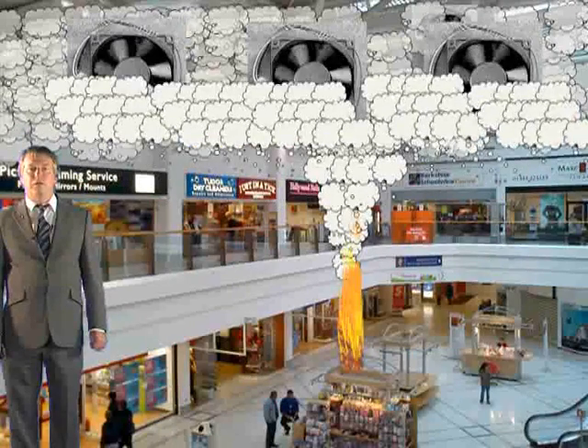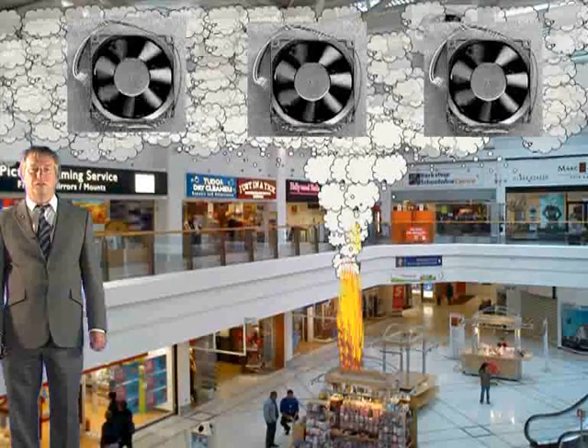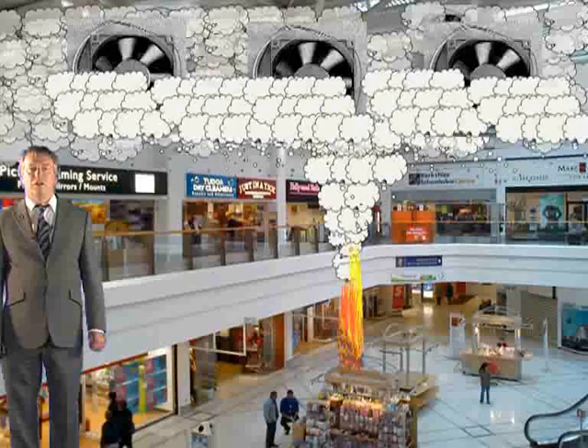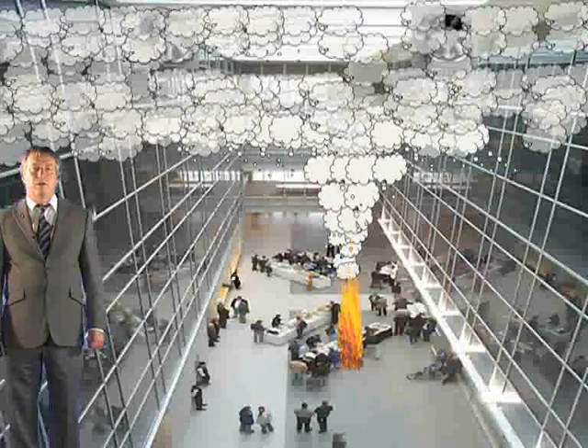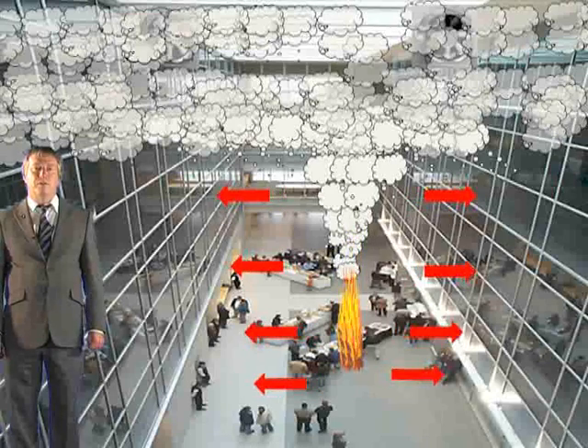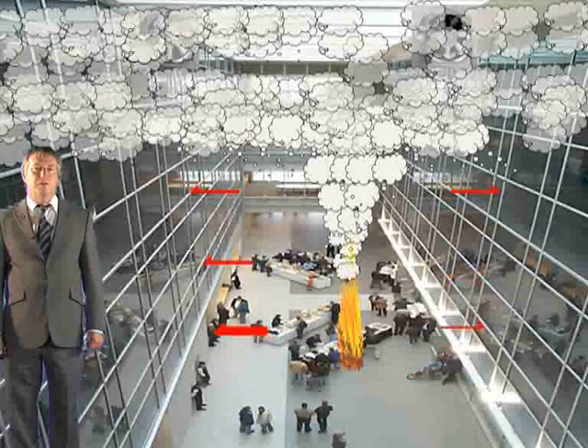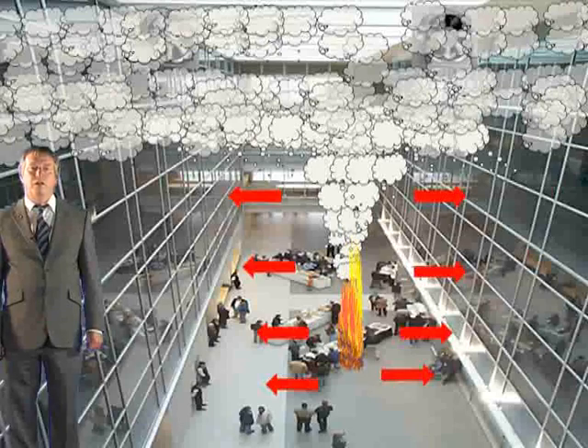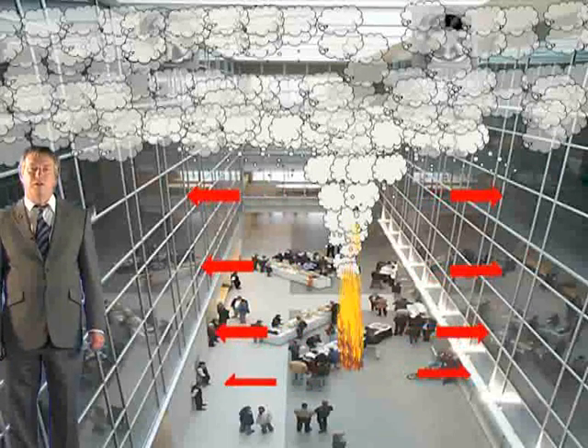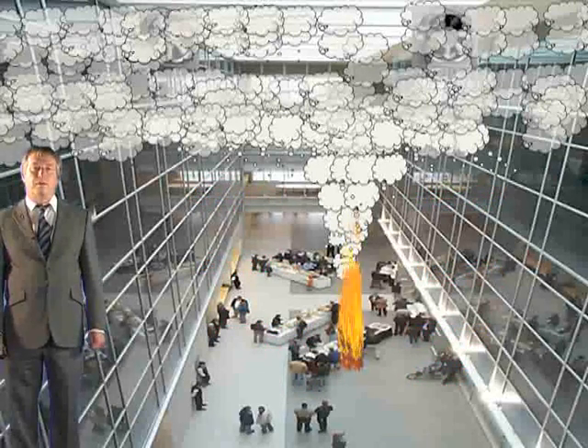Now, the heat can be vented by the smoke exhaust system to ensure that the heat flux to critical structural elements is kept below acceptable criteria. Another reason for keeping the temperature below a certain level is to enable you to specify materials with a lower than required fire resistance than the codes normally require.